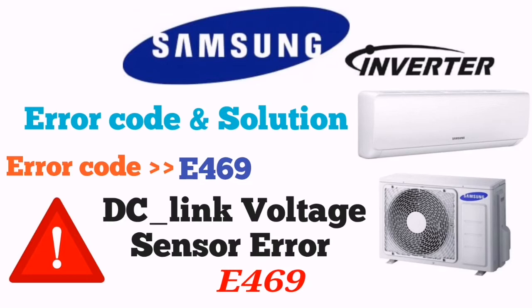the voltage of your reactor wire A in normal operation mode. The normal range should be 280 volt DC to 320 volt DC. And if the voltage is not correct, then you have to check the power input. Even if your power input is okay, then you have to check that the sensing voltage B is normal in operation mode. The normal range should be 0.2 volt DC to 4.8 volt DC.